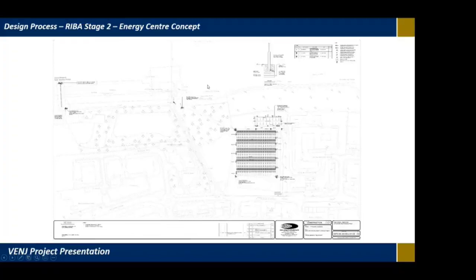On the actual bridge we've got the abstraction pumps that extract the water from the river and pump it via underground pipework back to the energy centre. That goes through the heat pump and then back out into the river, through a dedicated below ground pipework system that discharges the river water back into the river — so there's no chemical change to the water. It's filtered via rotary filters on the bridge and runs back to the energy centre; we're taking some of the heat out of the water and putting it back into the river again.